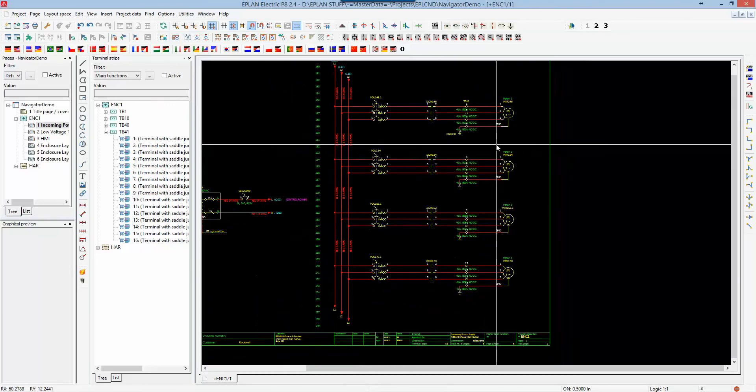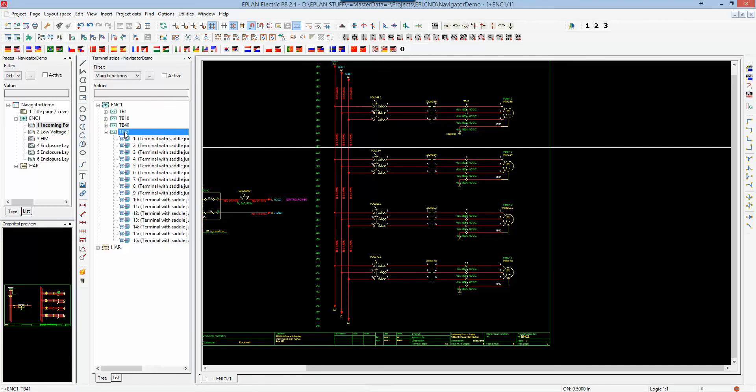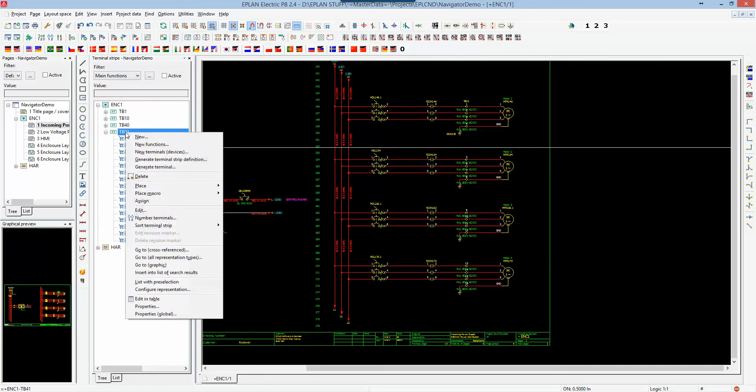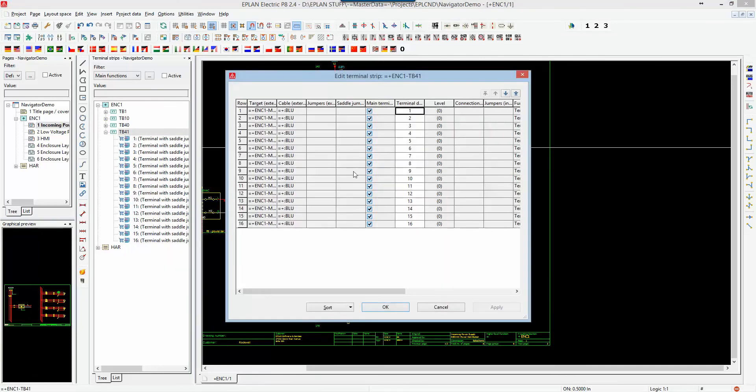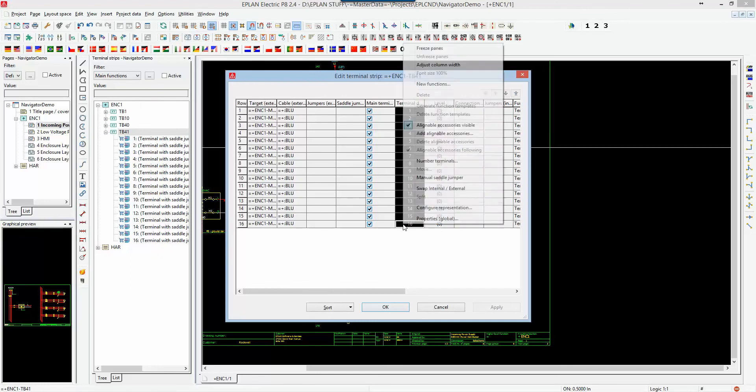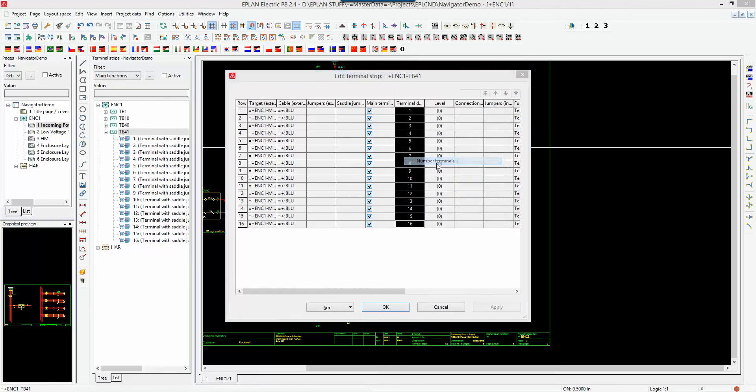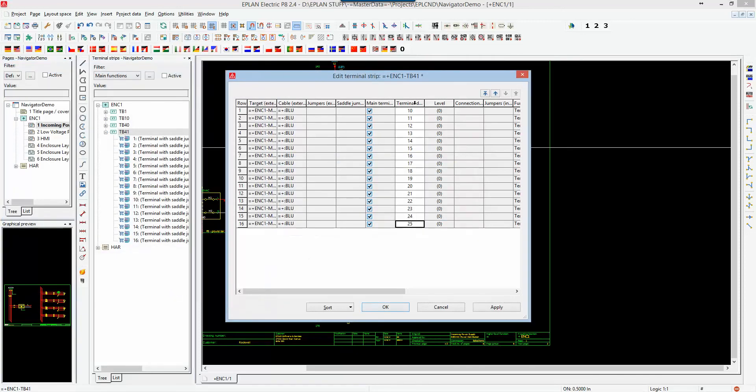And of course, I can modify, I can reposition also within the navigator, such as the terminal strip navigator. I can use here the edit functionality, which will permit me to renumber. If I need to renumber here, I can right-click and say, number terminals, and I can say start value 10, increment by 1, and as soon as I hit OK, I got this different incrementation.